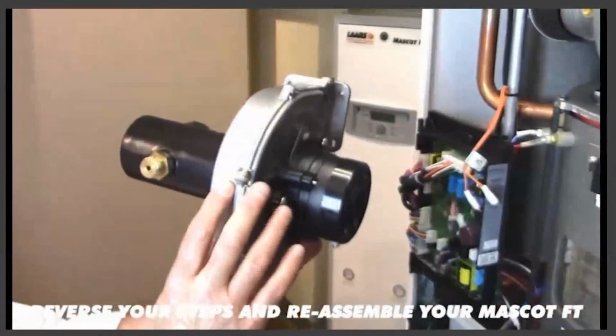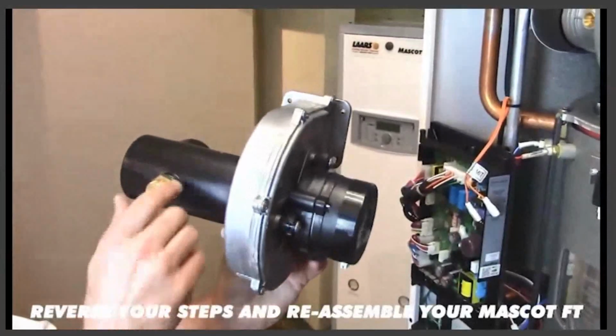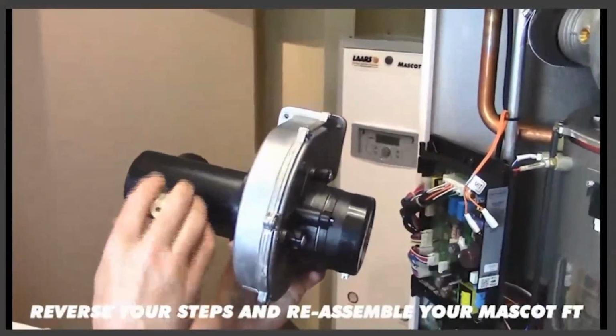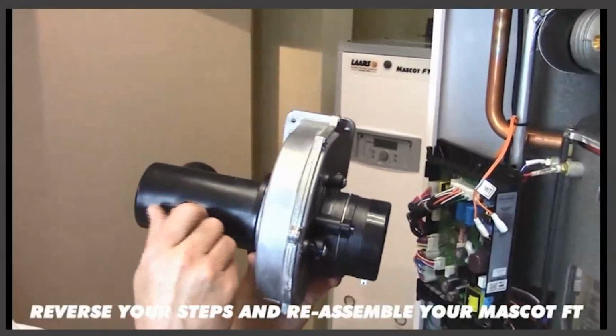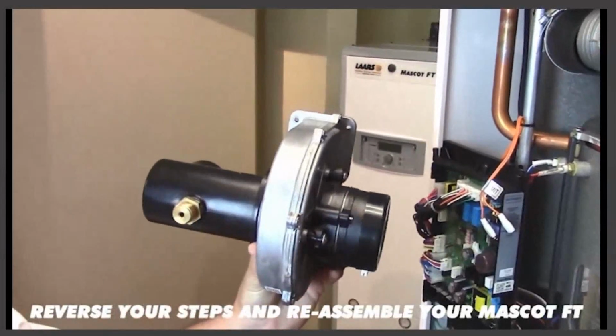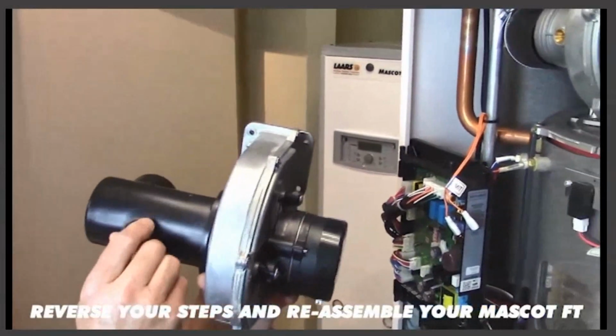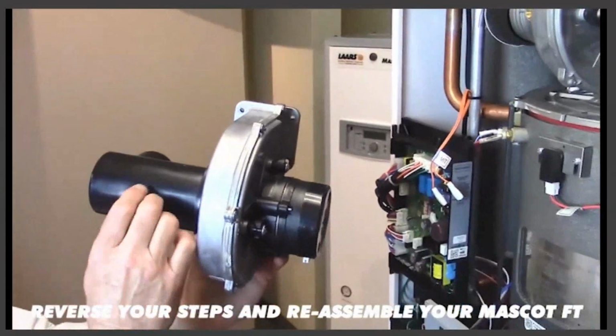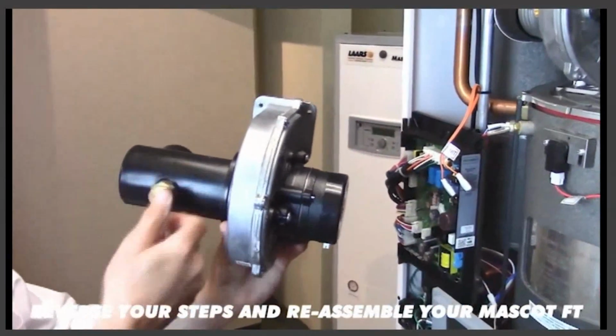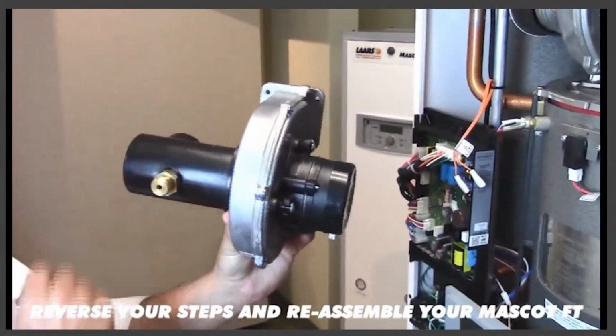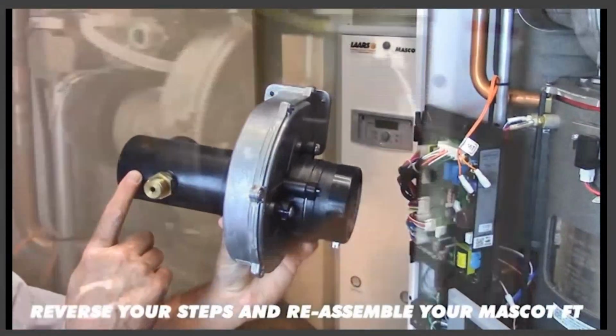This is showing the 140 blower with the orifice on the 140. This threads into position, so you do not have to remove that for removal of the burner plate. However, if you are putting a new orifice in or checking it, just make sure it's snug. Don't tighten down too much or you'll crack the plastic venturi of your mixing station.